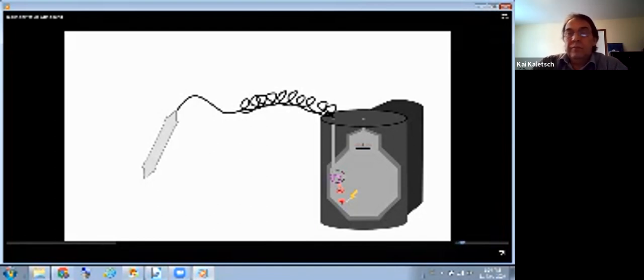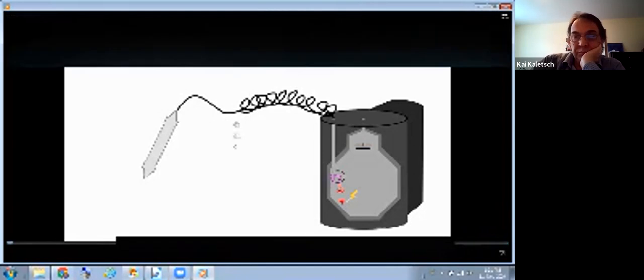The next morning you will see lots of counts and the sniffer won't be able to do its background subtraction properly because it assumes all counts at the beginning of the day are from the radon, not the radon decay products. So, let the sniffer run in clean air before shutting it off to flush out any radon, and turn it on in clean air the next time you use it to make sure the counts are still low.